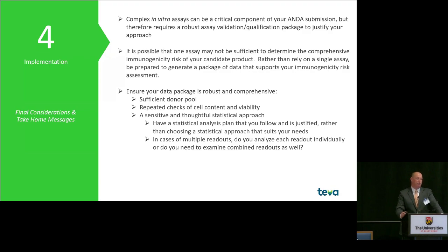In cases of multiple readouts, one fair question is, do you analyze each readout individually, or do you need to examine the combined readouts as well? I think that there's still research to be done on that front, so I will abstain from sullying the waters further with my own personal opinion, but just know that that may be a consideration for you. This one I will provide my opinion on: a blinded sensitivity and specificity check at your assay sensitivity limits is very helpful for you to verify and validate your sensitivity claims. So I would still suggest that as part of your validation.